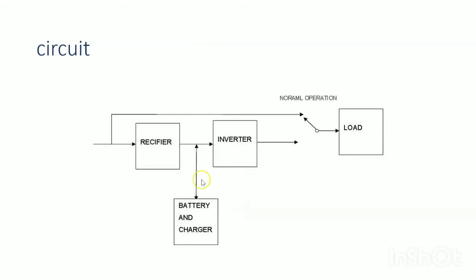Both online and offline UPS have a rectifier, battery or battery bank, inverter, and a switch. The key difference is that in online UPS, the rectifier-inverter path is the normal operation path, while the main supply path is only occasionally used. In online UPS, the rectifier-inverter always provides power to the load.